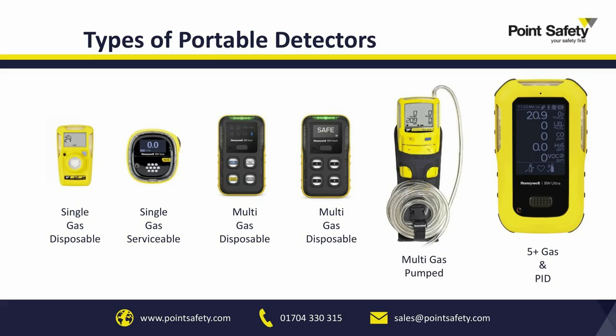So these are your most versatile, larger meters. They've got the option of pumps. They've got the option of probes. They've got a far greater range of sensors available to them across all the toxic range. The PID, infrared sensors for CO2, different types of sensor technology for their flammables, and they also have PID and VOCs available to them. So that's pretty much across the range. I've picked out Honeywell's product line here, but pretty much each manufacturer will have a line that supports the same categories across those areas.